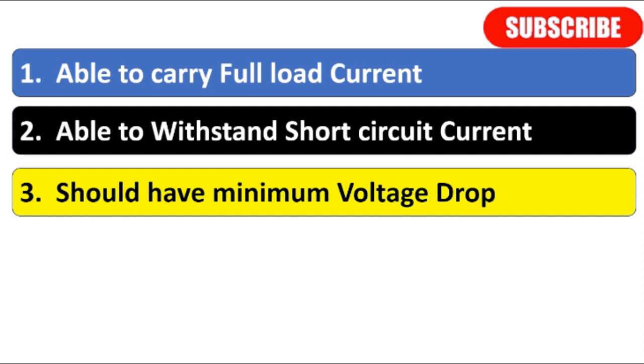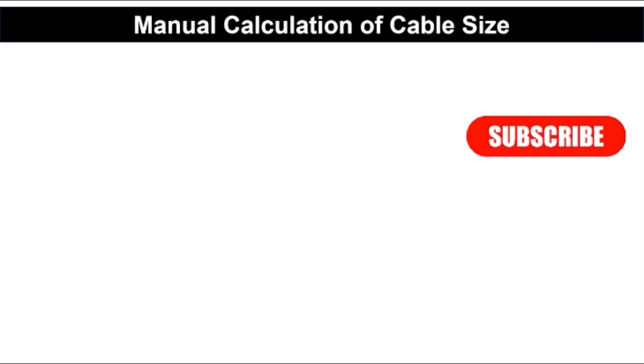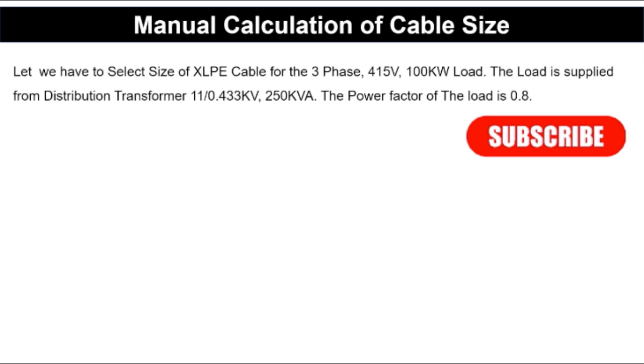To learn cable size calculation, we have taken an example. We have to select the size of an XLPE cable for a three-phase, 415 V, 100 kW load. The load is supplied from a distribution transformer rated 11/0.433 kV, 250 kVA. The power factor of the load is 0.8. First, we will calculate the load current.